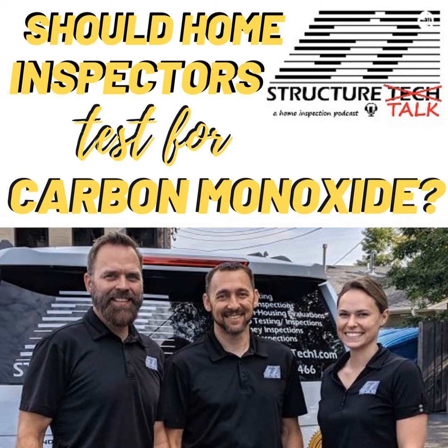But you said hood, but you meant to say draft fan, of course. Draft fan. Thank you. Yes, we can rely on you for your technicalities. Thanks for fixing that. And then you want to make sure that you're not drilling into a bend. Like if that flue takes a turn, you don't want to take a measurement right in a bend. And you want to stick your probe into that flue and have it go right into the center of the flue, I believe.